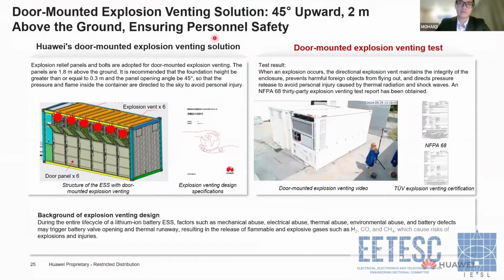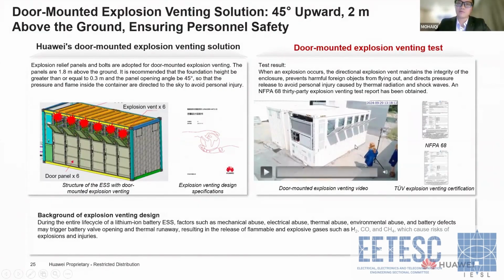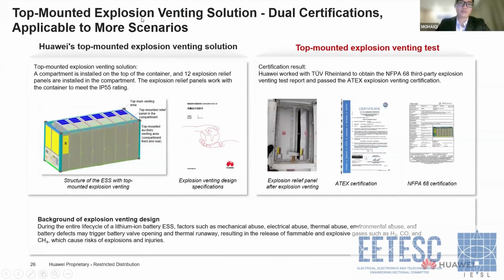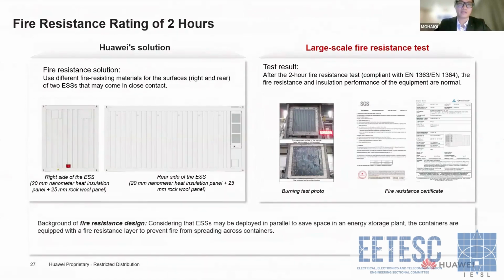And these are some explosion vent solutions. These are to prevent explosions from damaging people if someone is doing maintenance work and an explosion happens. There is a small video I want to show. Even people just 2 meters away from the door will not be damaged. And for the top mount explosion vent solution, this one is easier to see. If you are using the top mount and someone is in front of the door, the person will not be damaged. And these are some fire resistant ratings of 2 hours. After a large scale fire resistance test, our container cover can still remain stable. And if a fire accident really comes, then we can move it out and install a new one.